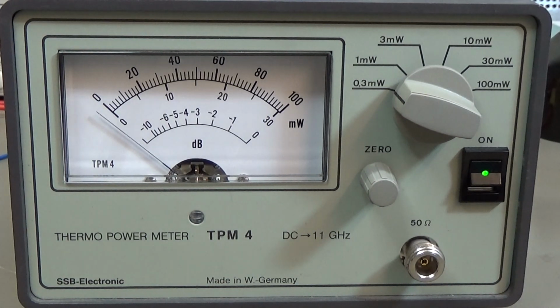Okay, anyway, let's start. First of all, you see it is already switched on, and the unit has been on for approximately 1 hour. That is important, because you should never do any calibration jobs if the unit is cold. It's the same for my frequency generator, which has also been running for longer than 1 hour.